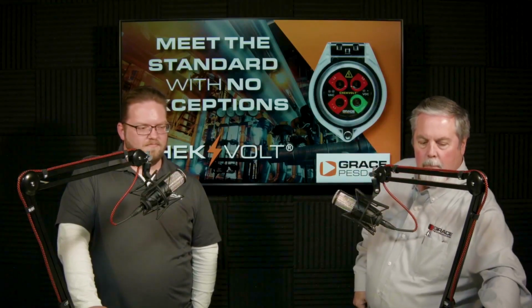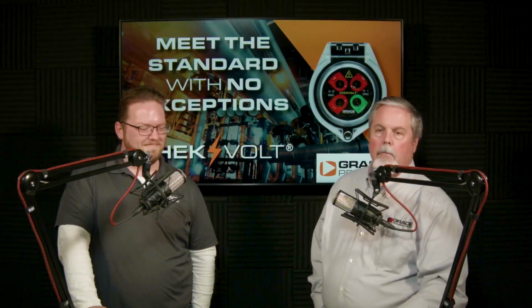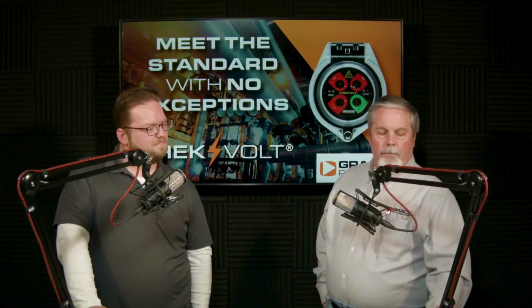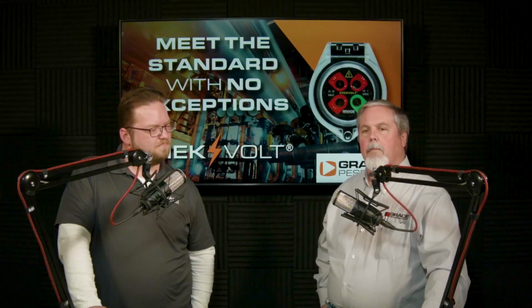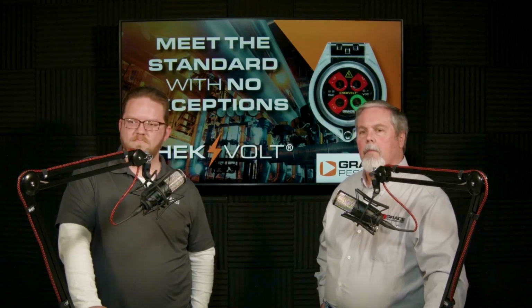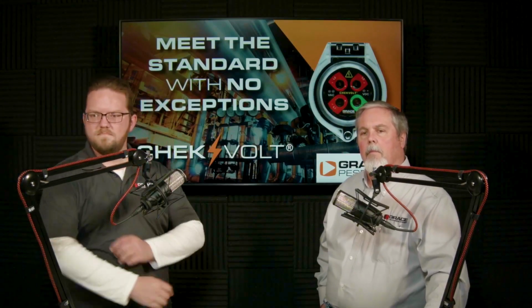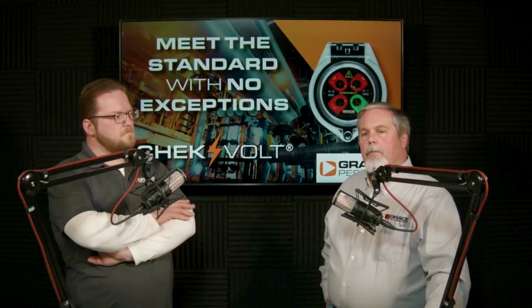And then we did have another question regarding CHEKVOLT. It's been popular. Yes. So let's see. Go back to chat here. The question was, do you have a self-checking meter for Live Dead Live that can plug into the CHEKVOLT instead of using a portable multimeter? This could help simplify non-electrical personnel and lockout tagout. I know last time we did CHEKVOLT, we talked about in the webinar, we had that Fluke proving unit that we were using as an example. Yep. I don't know if that's what we're getting at here, but you guys have a perspective?